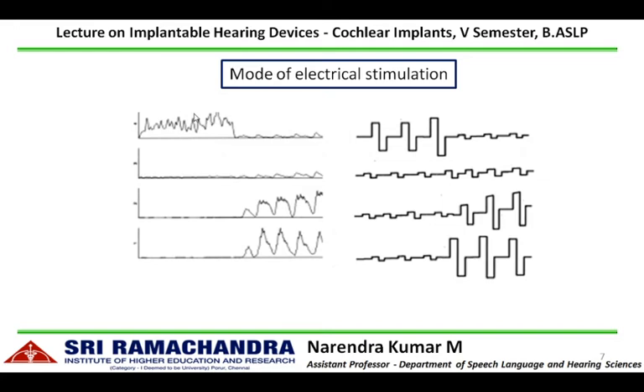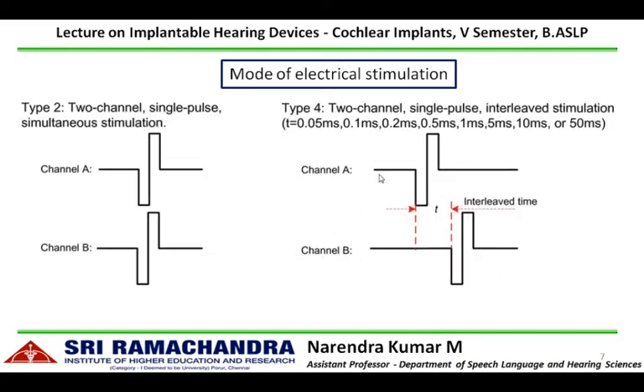Following amplitude coding is the mode of electrical stimulation. The extracted envelope can either be delivered as-is to the intracochlear electrode array, which is called analog stimulation — a continuous stimulation through the electrode contact area. Alternatively, if the analog signal is converted to digital form using a train of biphasic pulses, that is called pulsatile stimulation. Electrical stimulation is therefore of two types: analog and pulsatile.